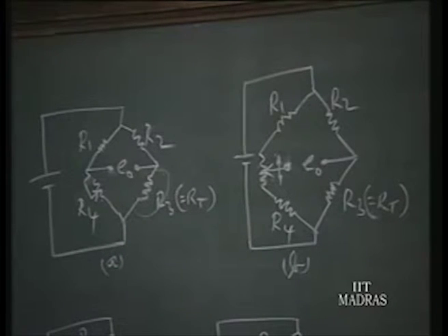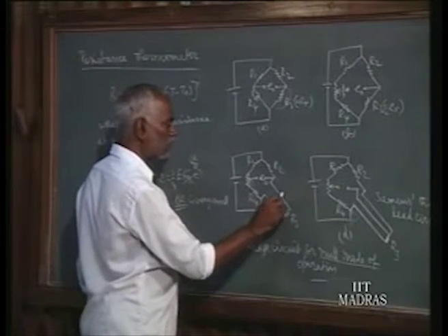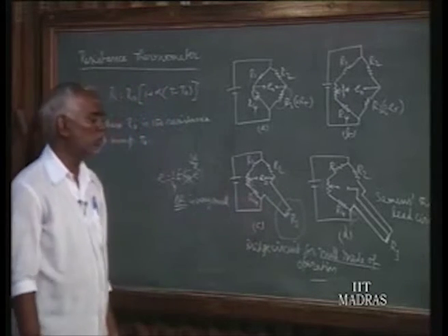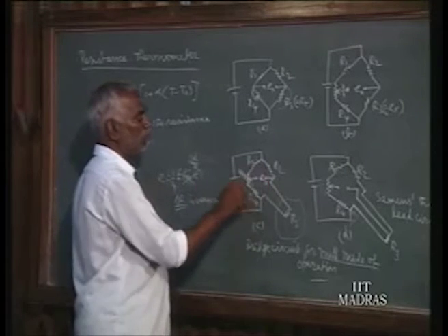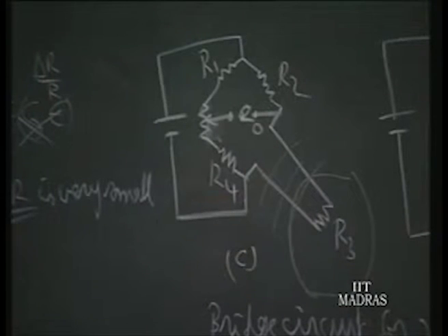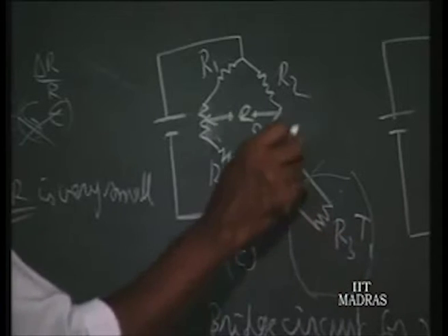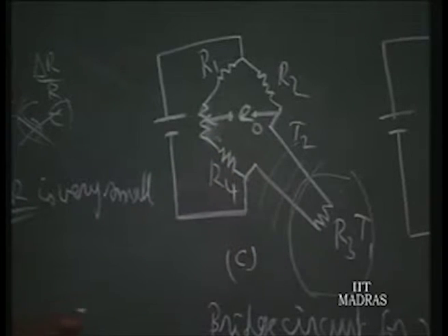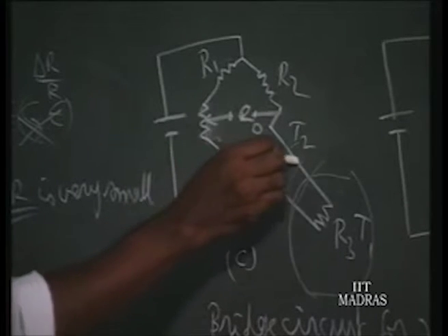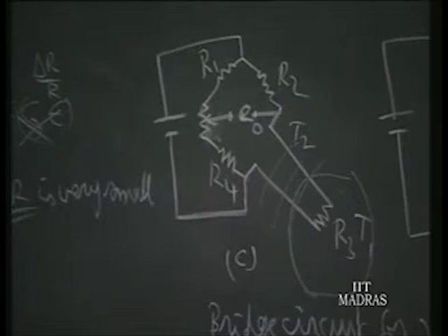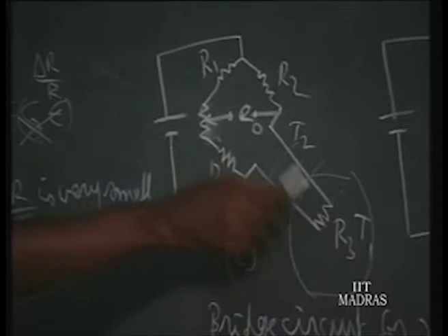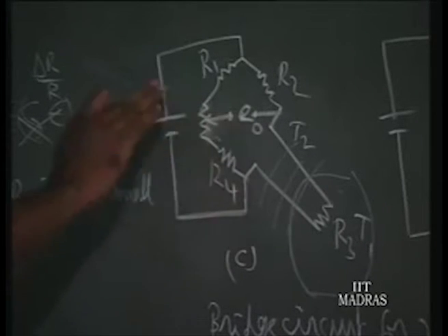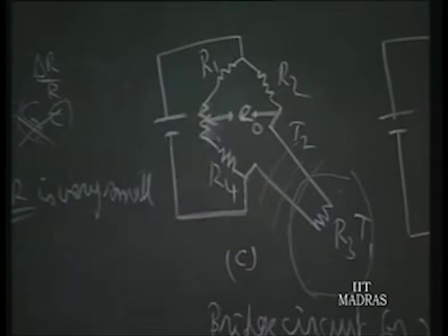In actual practice, we take R3 to a distant place from the control room. The lead wires are brought to the control room for building the bridge there. These lead wires may be subjected to different temperatures T1 and T2. Due to temperature T2, the resistance of the lead wires may change, and that forms part of the R3 arm of the bridge. That will affect the balancing of the bridge, but it is not due to temperature in R3 — so this is an error source.